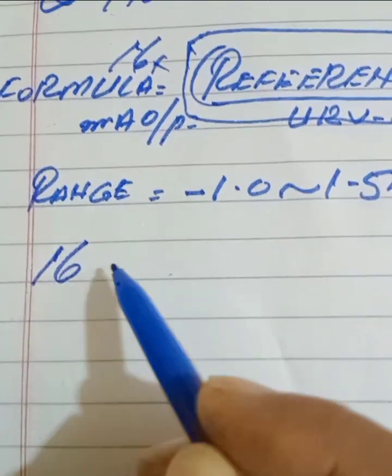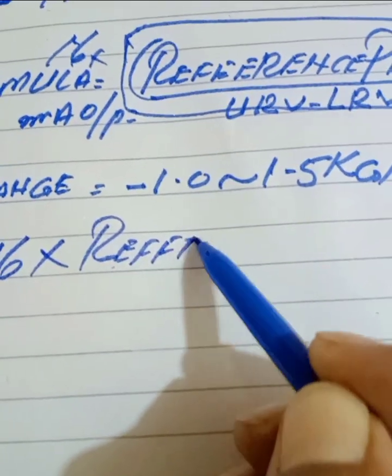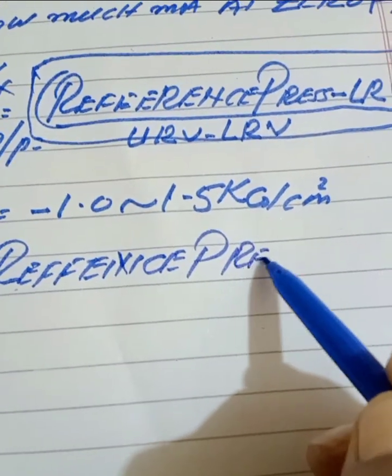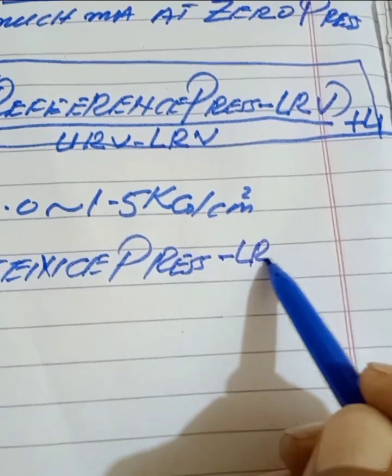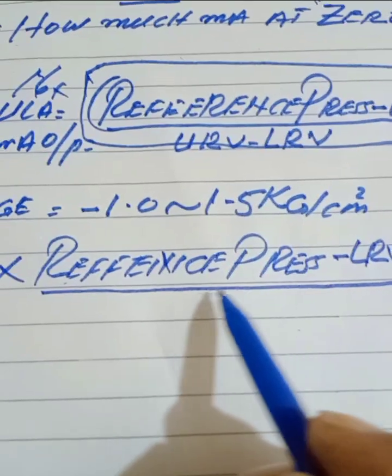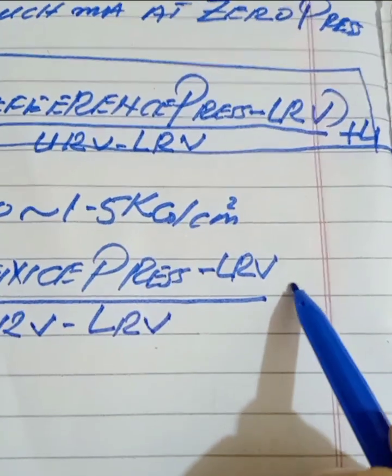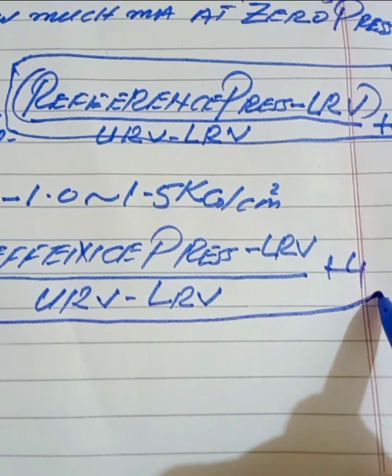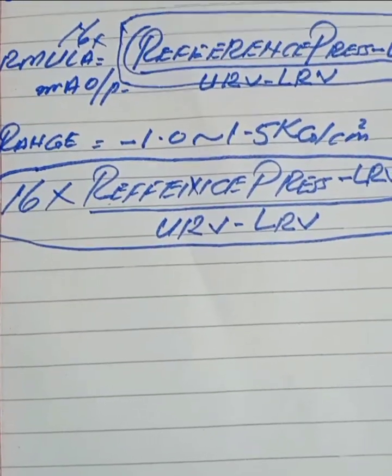We expand the formula as: 16 into (reference pressure minus LRV), divided by (URV minus LRV), plus 4. This is our formula. As per this formula, we will calculate the current value. Our transmitter range is minus 1.0 to 1.5 kg per cm squared. Let's put in the values.